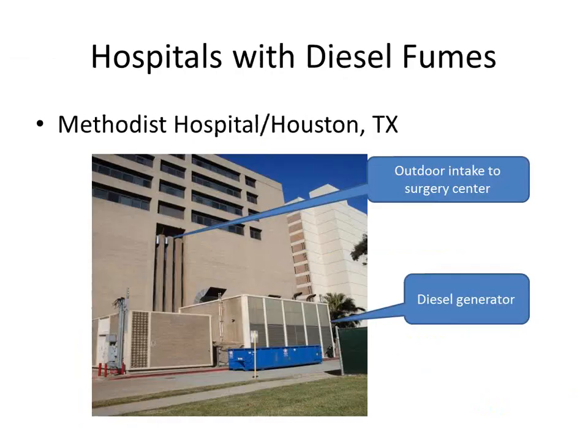This is Methodist Hospital down in Houston, Texas. You can see where the generators are located. You can see where the outdoor intake to the surgery center was. They had a lot of problems with the surgical centers having to be shut down. And I can hear a lot of snickering out there. How did this ever get designed this way? I don't have the answer to that question.